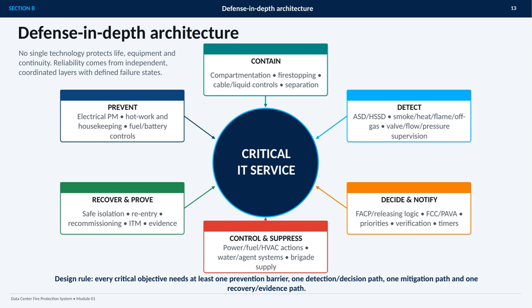The Fire Alarm Control Panel, releasing logic, communications, priorities, verification, and timers coordinate the response. Control and suppression may then act on power, fuel, and HVAC systems, while deploying water or agent systems. Finally, recovery requires safe isolation, controlled reentry, recommissioning, inspection, testing, and maintenance with evidence preserved. The design rule is simple. Every critical objective needs prevention, detection and decision, mitigation, and recovery paths.